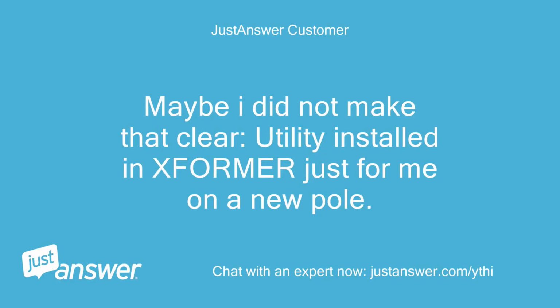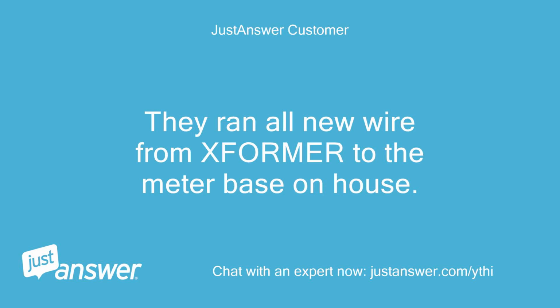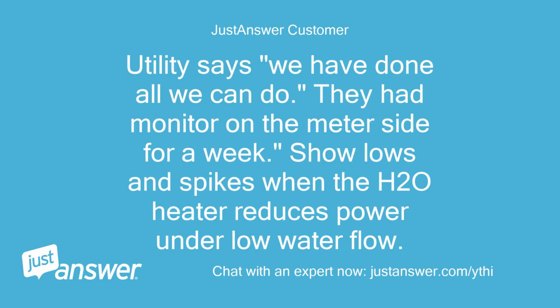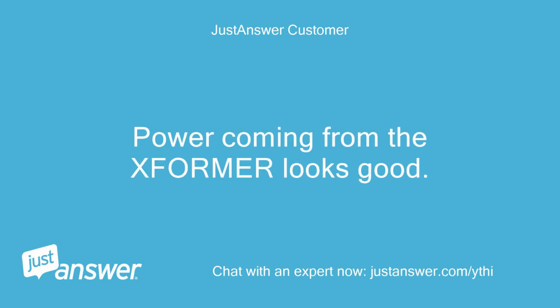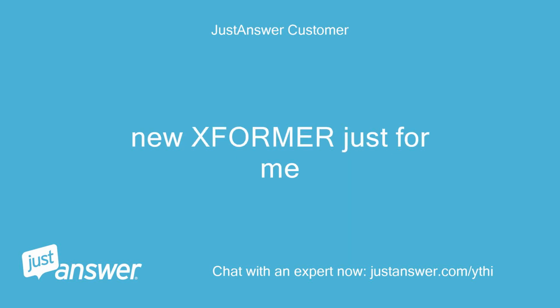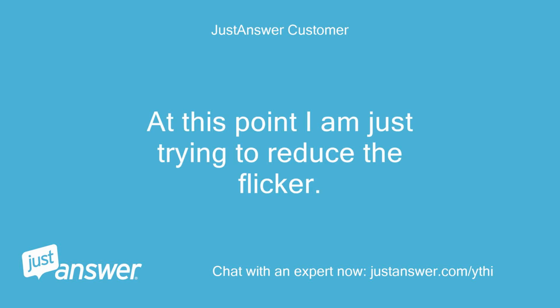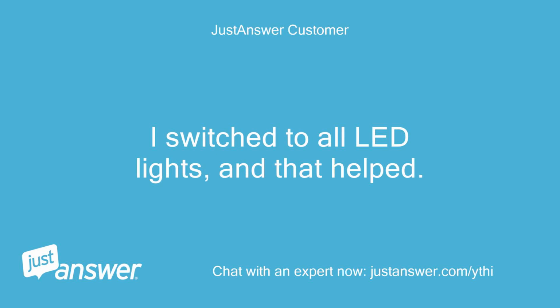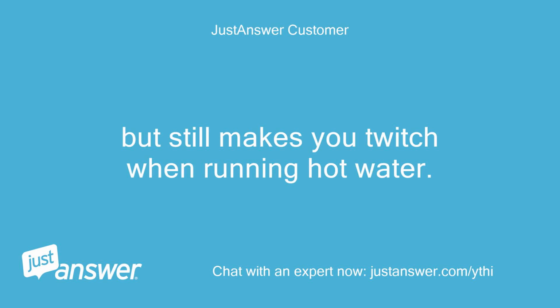Maybe I did not make that clear. Utility installed a transformer just for me on a new pole. They ran all new wire from transformer to the meter base on house. Utility says we have done all we can do. They had a monitor on the meter side for a week. It shows lows and spikes when the H2O heater reduces power under low water flow. Power coming from the transformer looks good. New transformer just for me. At this point I am just trying to reduce the flicker. I switched to all LED lights, and that helped. But it still makes you twitch when running hot water.